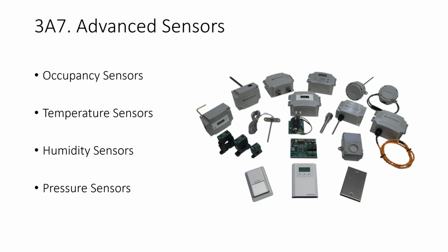The next component I'll talk about is sensors. Sensors are really important to keep our AC system efficient. There are numerous types of sensors which air conditioning systems use, including occupancy sensors, temperature sensors, humidity sensors, and pressure sensors. From a safety perspective, there are CO2 sensors and smoke sensors as well. In a multi-residential building, if there's smoke, we can detect it through the return air, shut down our AC system, and the fire alarm goes off. It's a safety device, and it's a must in multi-residential buildings as well as commercial buildings.